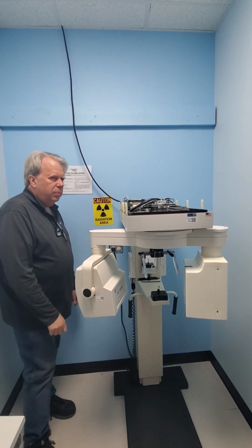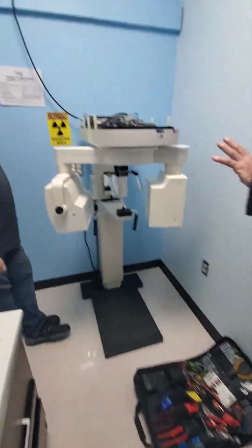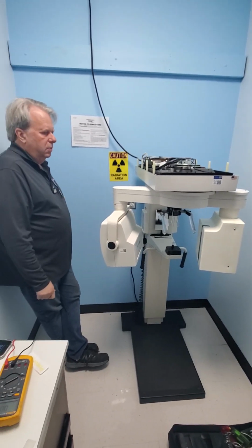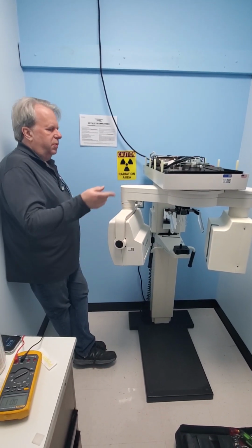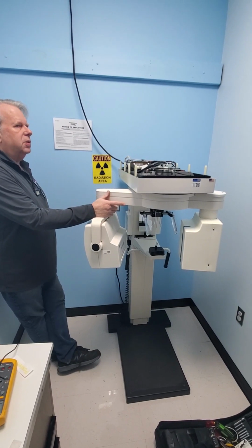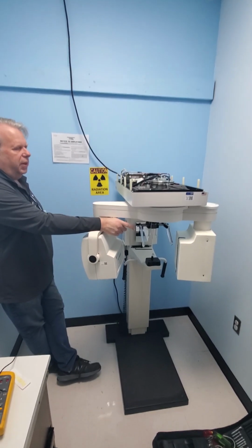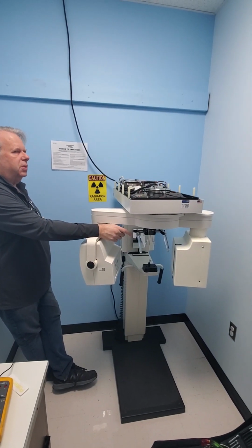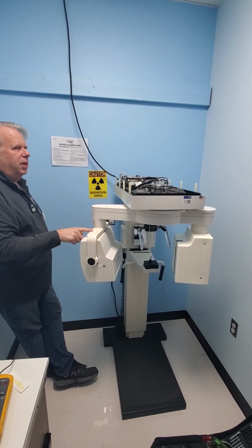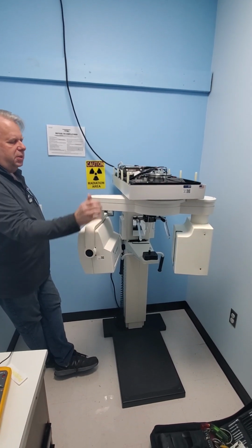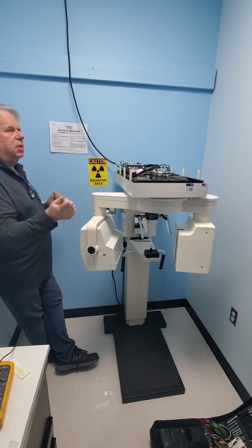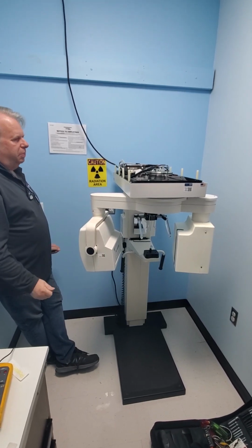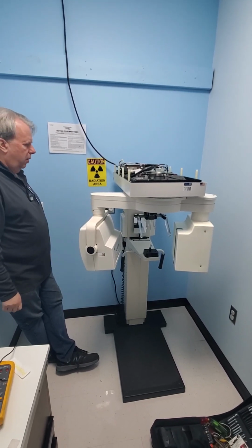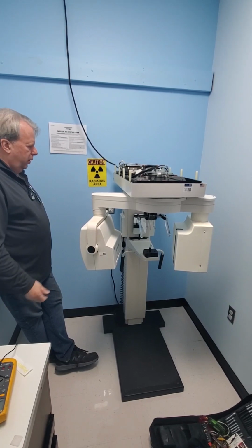Well, it seems like if you're adjusting the tube, you're more likely to get it skewed than if you're adjusting the sensor. Not necessarily. If the sensor was aligned properly at installation, it's unlikely that they move the sensor during use. So more likely, if it's aligned properly, somebody bumps into this and you get it skewed. You just need to put it back where it's supposed to be, back to center. I got you. Okay, that makes sense.